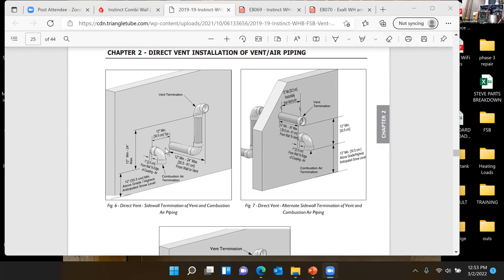And one thing to note on here, and this has been talked about a lot, is the exhaust off the wall to the face of this 90, 12 inches. That's pretty far. And we've had some inspectors kind of hit on that. We've had people ask if we can reduce that or do we really need to do that? So I think you're going to see that change down the road. I don't think we have to have that on a lot of installations. Our engineers are looking at it. We're testing some things. It's on the docket.